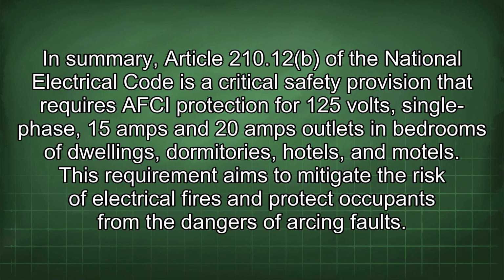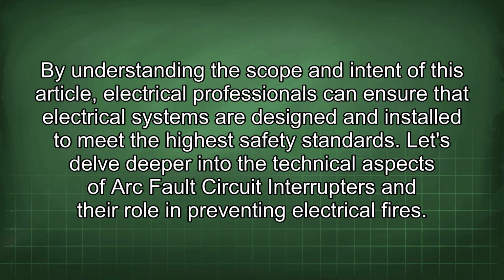In summary, Article 210.12 of the National Electrical Code is a critical safety provision that requires AFCI protection for 125 volts, single-phase, 15 amps and 20 amps outlets in bedrooms of dwellings, dormitories, hotels, and motels. This requirement aims to mitigate the risk of electrical fires and protect occupants from the dangers of arcing faults. By understanding the scope and intent of this article, electrical professionals can ensure that electrical systems are designed and installed to meet the highest safety standards.